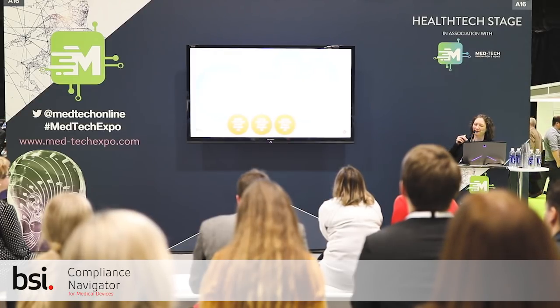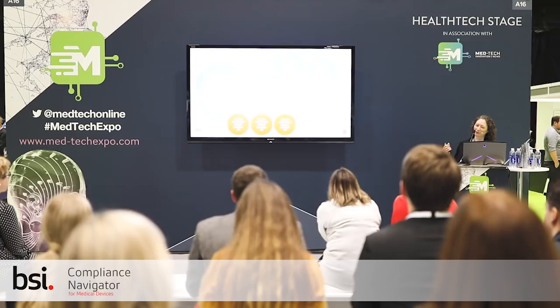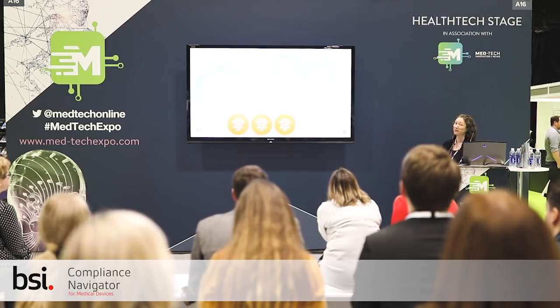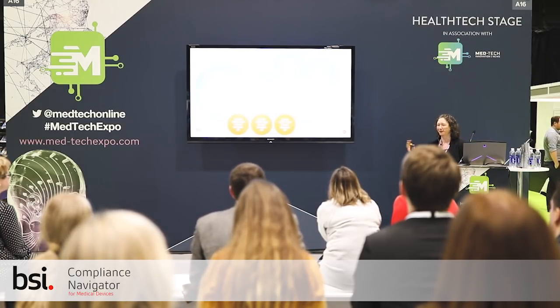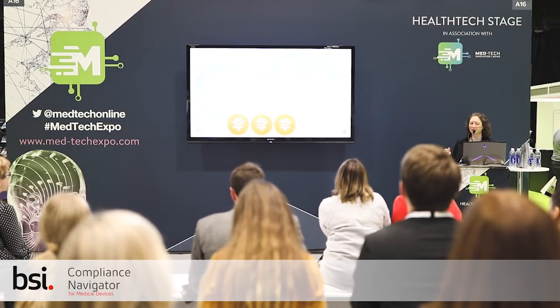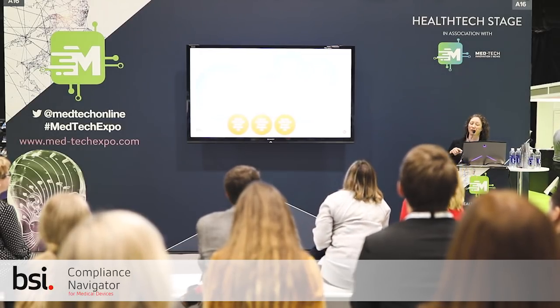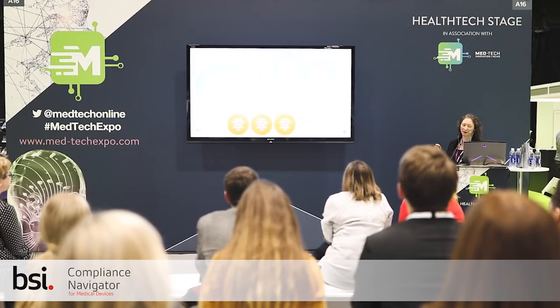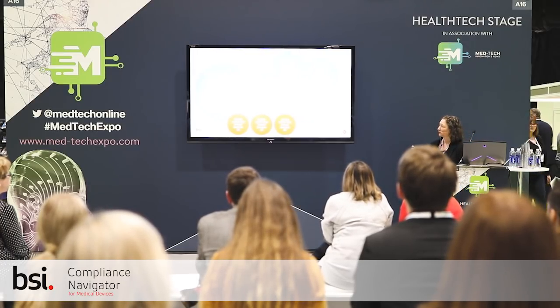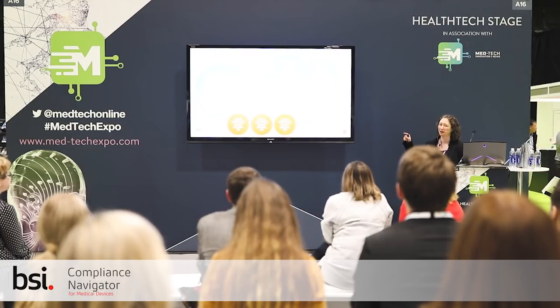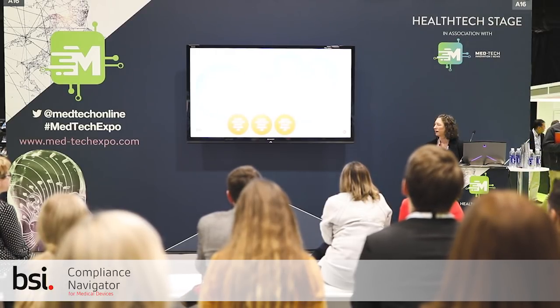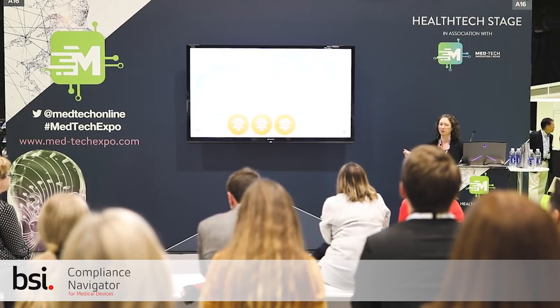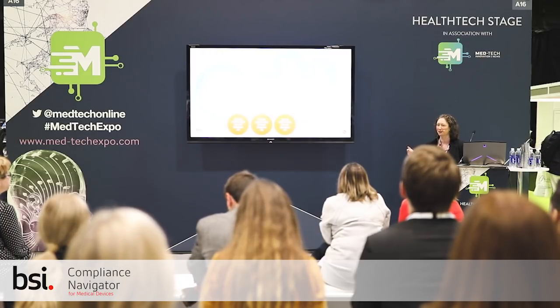So it says eliminate or reduce the risks as far as possible through safe design rather than informing users. But then when it talks about informing users, it says provide information for safety warnings and contraindications by informing users, and then where appropriate, training to users. Under the MDR, it only talks about reducing the risk. It doesn't give you options for how you might do that. And I think this is really key, that it's starting to say that you might need to include training as a specific tool to reduce risk.